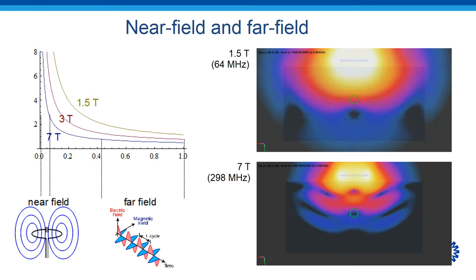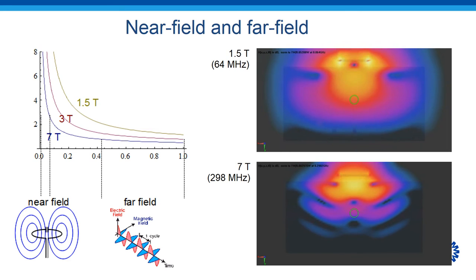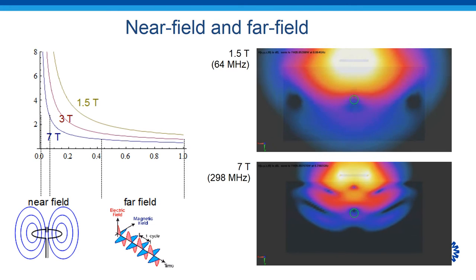This graph shows that for higher field strength or higher frequencies, the wavelength gets smaller, but also the near field gets smaller, which is beautifully depicted by the two movies on the right, where you can see a region of interest at 10 cm depth for a loop coil emitting B1 field into a tissue-like phantom. At 1.5T, the region of interest is very much in the near field.